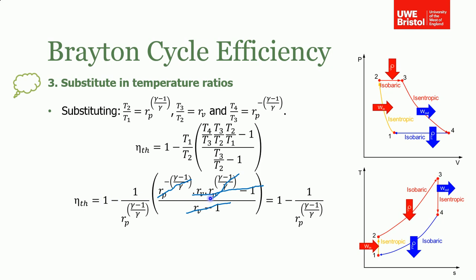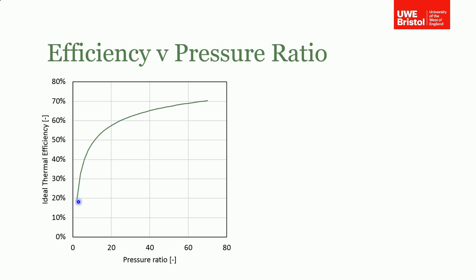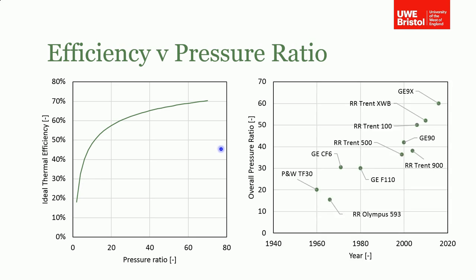This is shown graphically: ideal thermal efficiency on the vertical axis versus pressure ratio on the horizontal axis, confirming that increasing pressure ratio increases ideal thermal efficiency. A historical timeline also shows that from early Pratt & Whitney gas turbines through to the latest GE variants, pressure ratio has increased threefold — from around 20:1 up to 60:1 — driving ideal thermal efficiency from roughly 56–57% in the late 1950s up toward 69–70%.